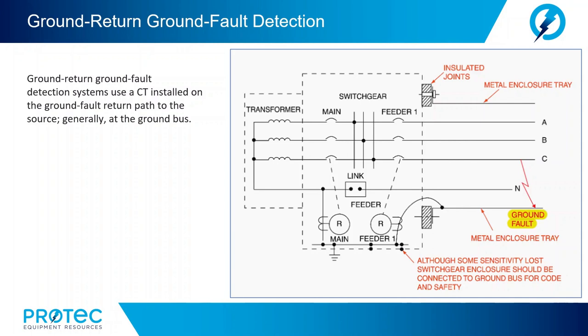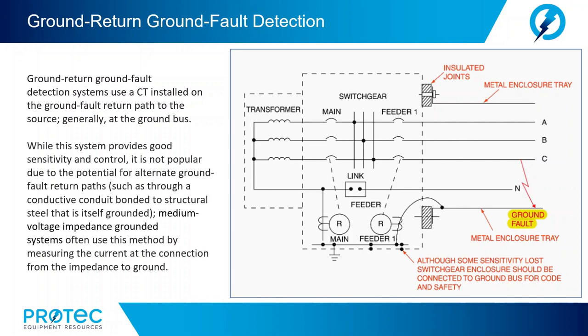Ground return ground fault detection systems use a CT installed on the ground fault return path to the source, generally at the ground bus. While this system provides good sensitivity and control, it is not popular due to the potential for alternate ground fault return paths, such as through a conductive conduit bonded to structural steel that is itself grounded. Medium voltage impedance grounded systems often use this method by measuring the current at the connection from the impedance to ground. Ground differential protection systems can be considered a subset of ground return detection systems; CTs are installed in the ground fault return path of each feeder, and if the current measured differs from the sum of the other CTs, the system operates.